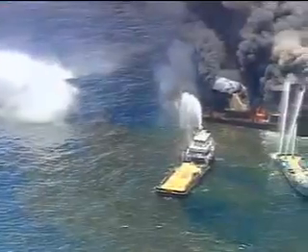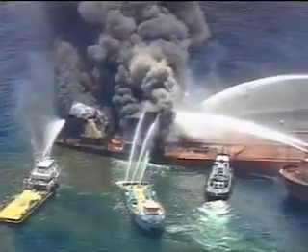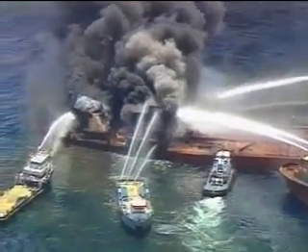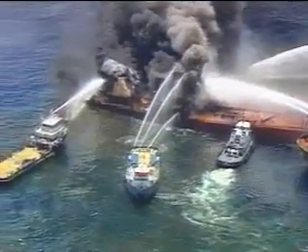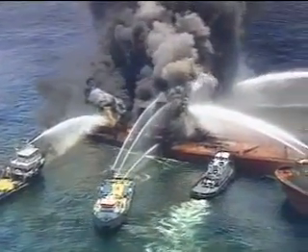Approach the fire down low and stay low where the cooler air is. Again, you probably only have about 17 seconds worth of extinguishing agent, so a direct sweeping motion is most effective. If other methods fail, all personnel may be evacuated from the area, so a fixed, closed system such as halon or CO2 can be used.